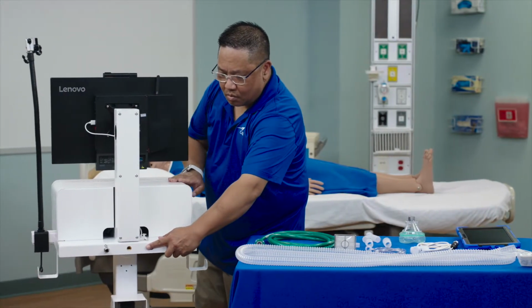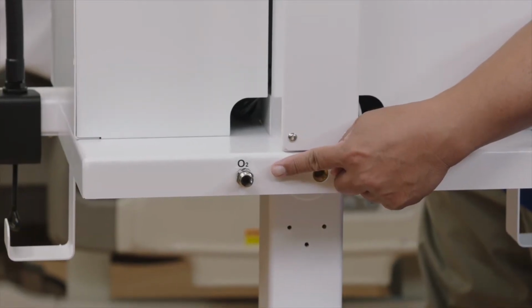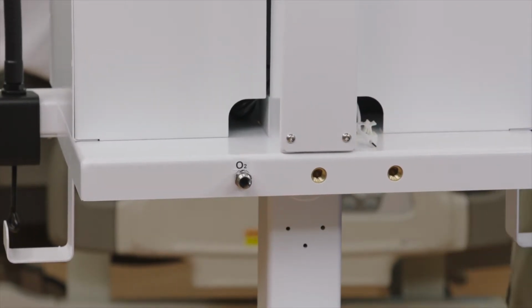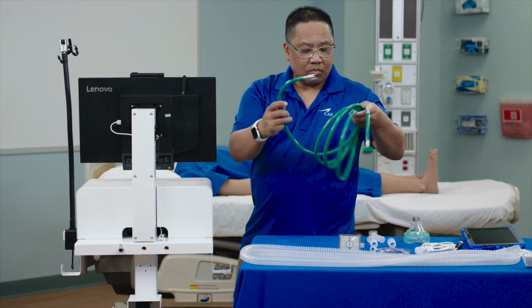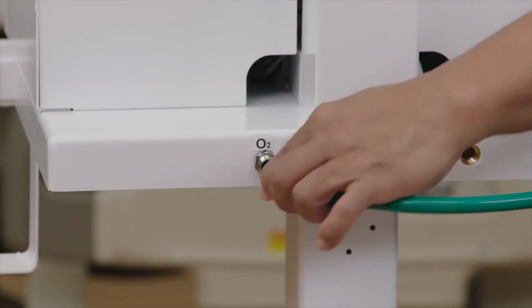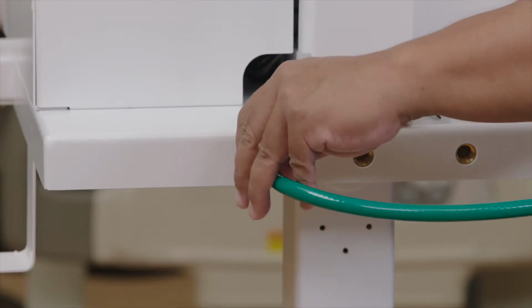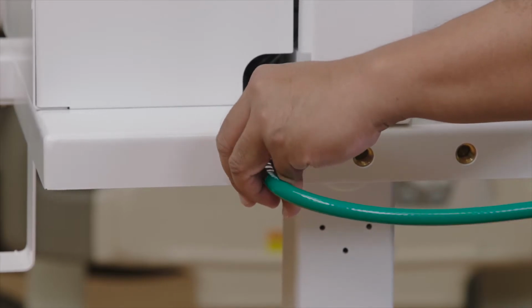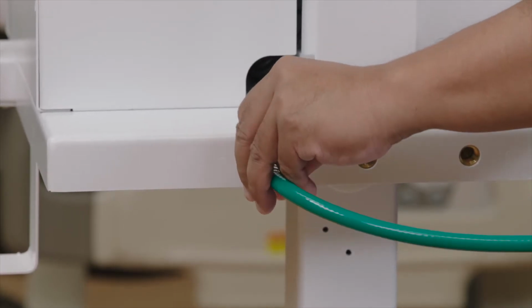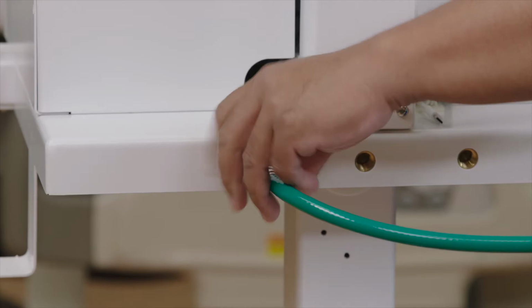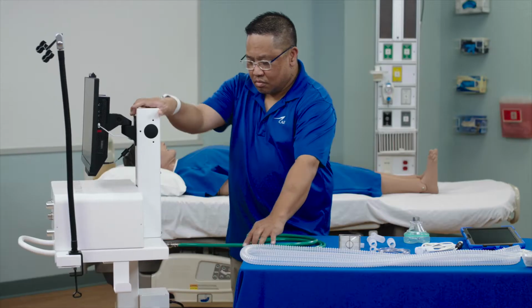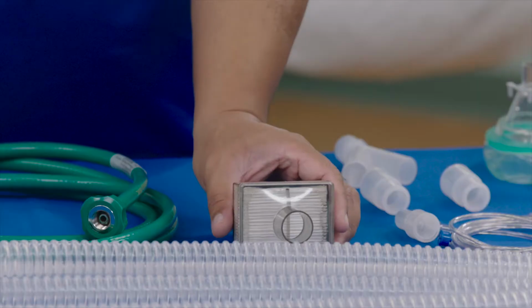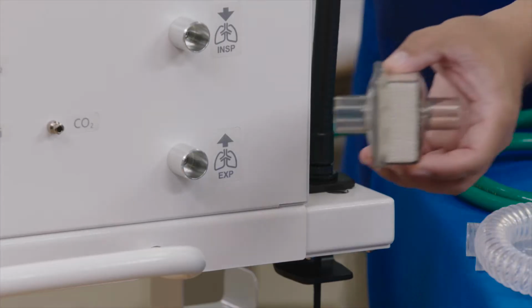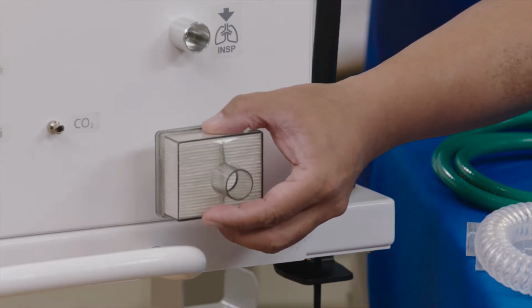Connect the oxygen hose to the back of the medical cart at the appropriate labeled port. Insert the opposite end of the oxygen hose into the simulated oxygen source. Never attach the hose to a real gas source. These are intended for simulation purposes only. Note, colors of hoses may vary depending on whether the ISO or US configuration was ordered. Connect the filter to the front panel of the cart where the port is labeled EXP.